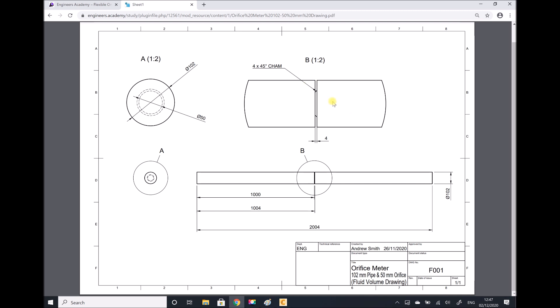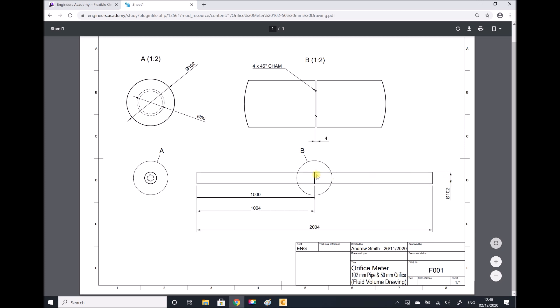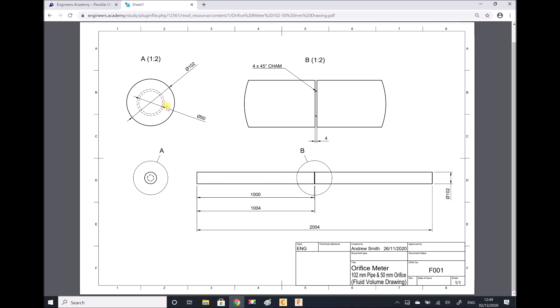Now, what we are going to be doing is measuring the pressure drop across that orifice plate. The first step is to create the volume, or create the geometry in Fusion. Once we have that volume, we can export that to Autodesk CFD, and we can begin to evaluate the pressures and velocities within this system. Our orifice plate has a thickness of 4 millimetres, it has a 45 degree chamfer, and we have 1000 millimetres upstream and 1000 millimetres downstream of the orifice. The total length is 2004 millimetres. The diameter of our pipe is 102 millimetres, and the diameter of our orifice is 50 millimetres with our 45 degree chamfer on the leading edge.